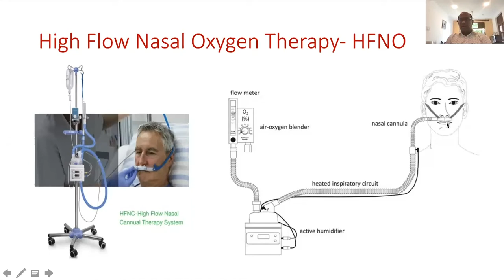We usually commence with a low flow rate, starting with 15 to 30 liters per minute, and we escalate gradually up to 40 to 60 liters per minute. It is important to check the hospital capacity of oxygen, which determines whether we can deliver intermittent high flow oxygen, because a high amount of oxygen is utilized in high flow nasal oxygen therapy. So always check the hospital oxygen capacity. And here again, the saturation target is 92 to 96, for COPD patients 88 to 92.